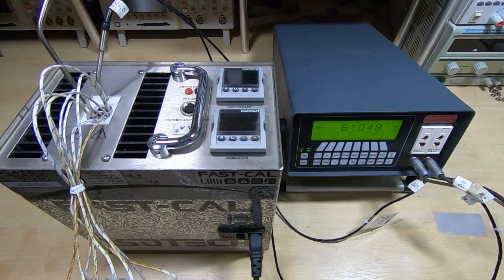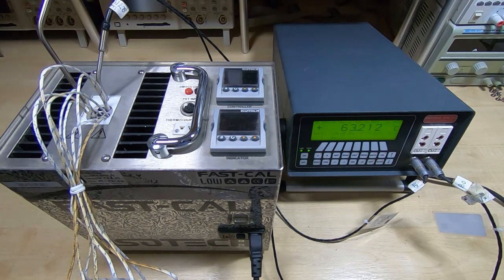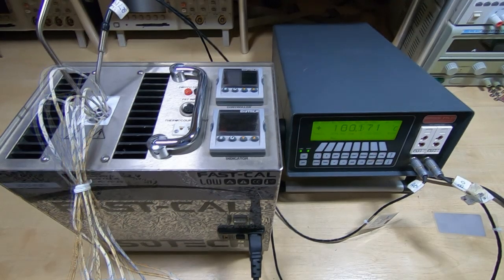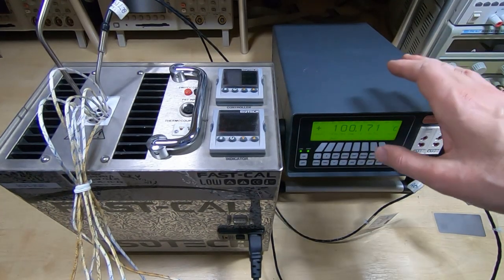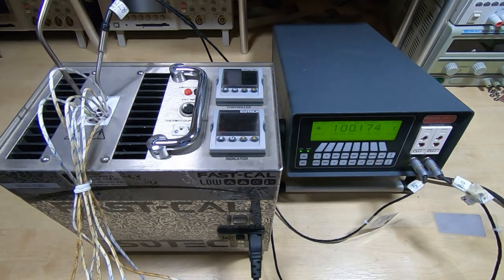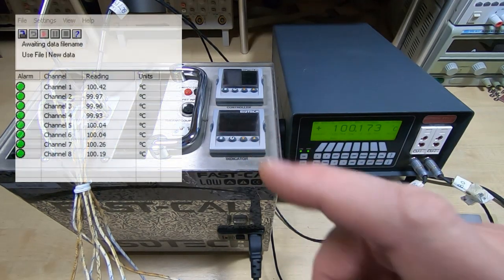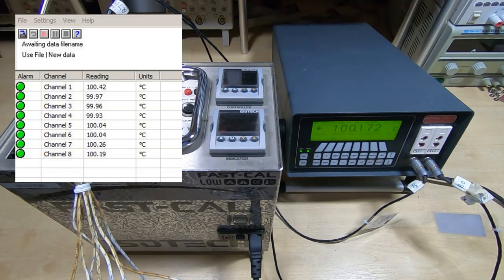Okay, so I'll let this settle at 100. We'll have a final look at that temperature, and then hopefully that will give you a good idea as to the approach I take to make sure I'm not getting errors with the actual sensors I'm using. Okay, so we've settled to 100 degrees. We'll take a screenshot again, and as you can see, we are still well within our target limits.